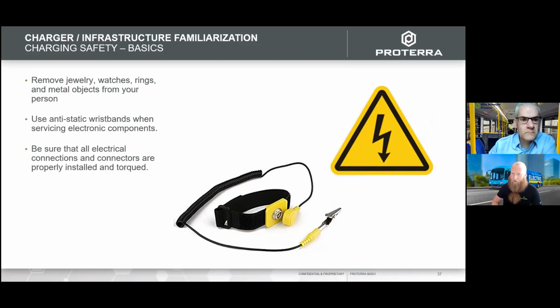And then finally, be sure that all electrical connections and connectors are properly installed and torqued. The reason I say that is that most chargers go through significant heating and cooling cycles on a regular basis. So think of this along the lines of expansion and retraction. As these connectors and fasteners continue to expand and retract back to their normal size, there's always the possibility they'll loosen up, or a connector will back off from its properly seated position.